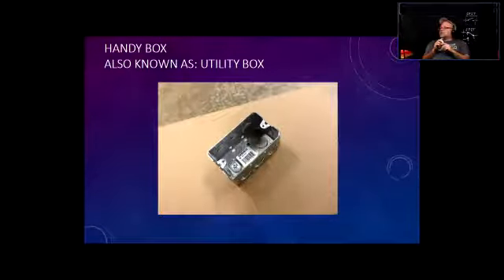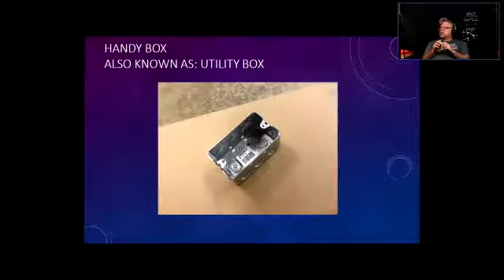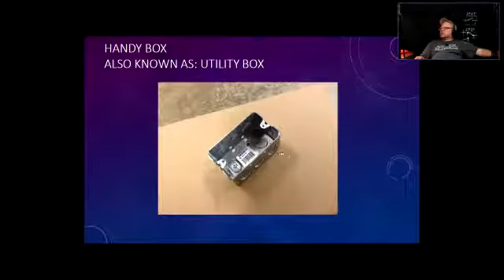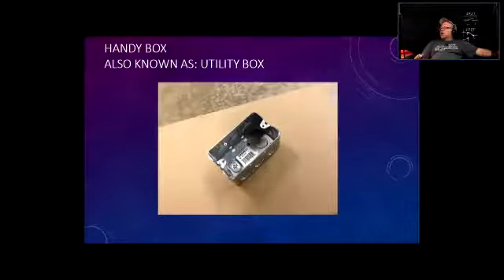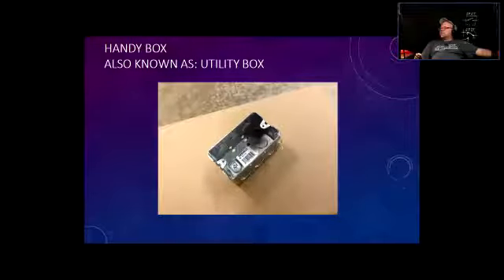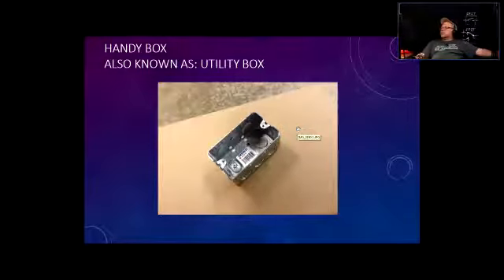Common terminology: handy box – you probably see this all over the place. It's also called a utility box. You can mount it as a surface mount or flush with the wall. It's a single gang box, but it is not gangable, because you would have to physically cut the metal to join them, which would modify an already-made device – so it's only used as a single gang box.